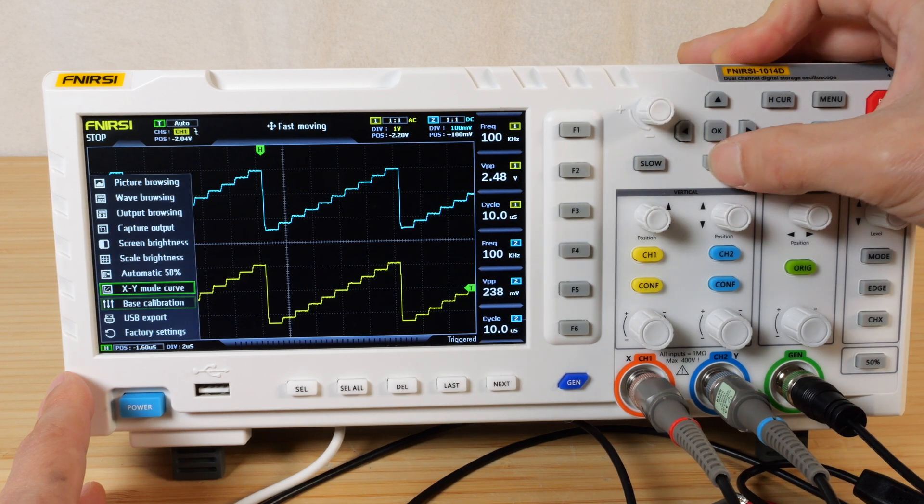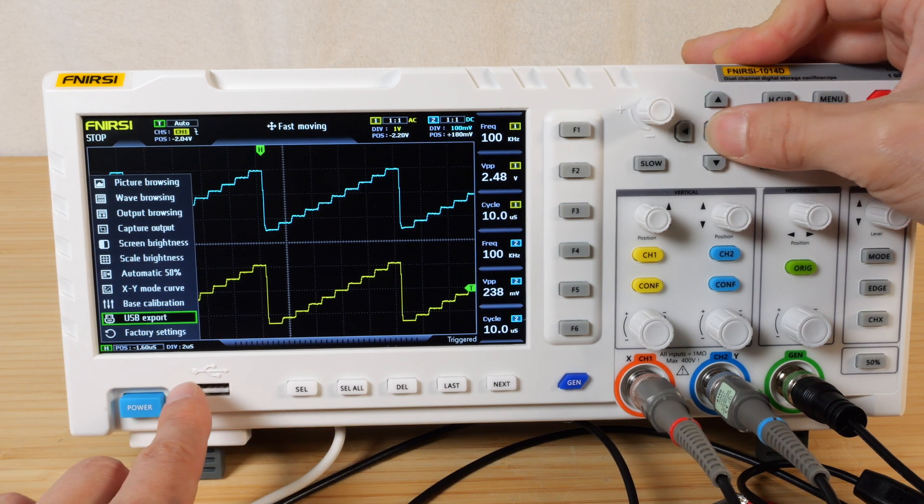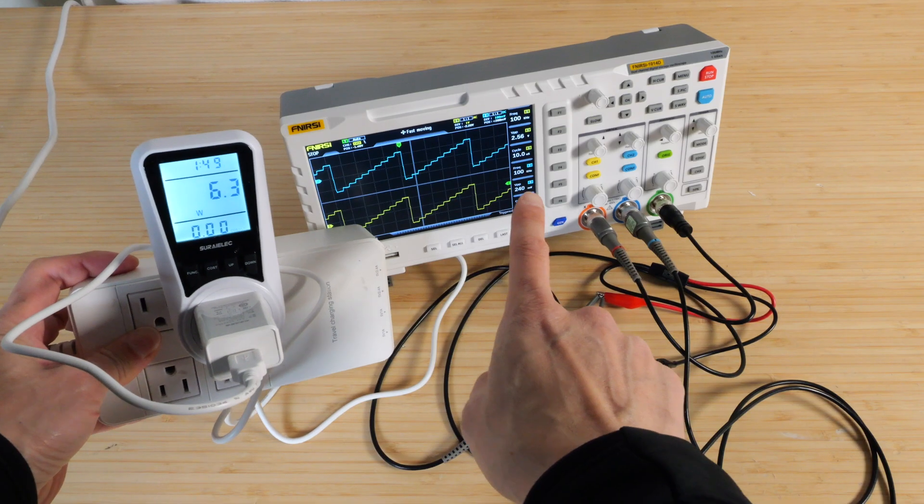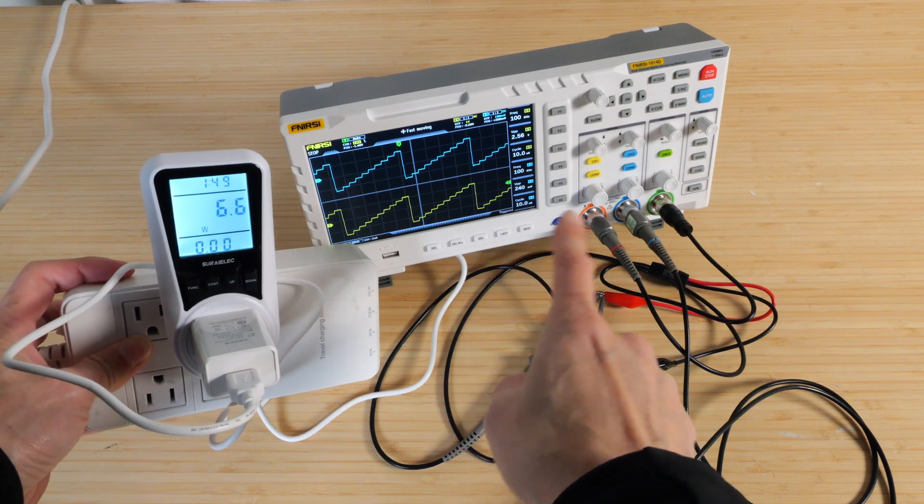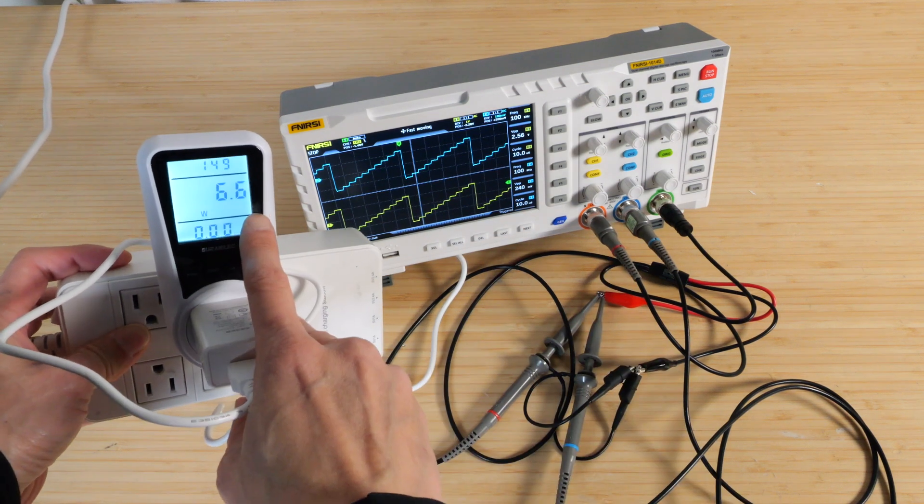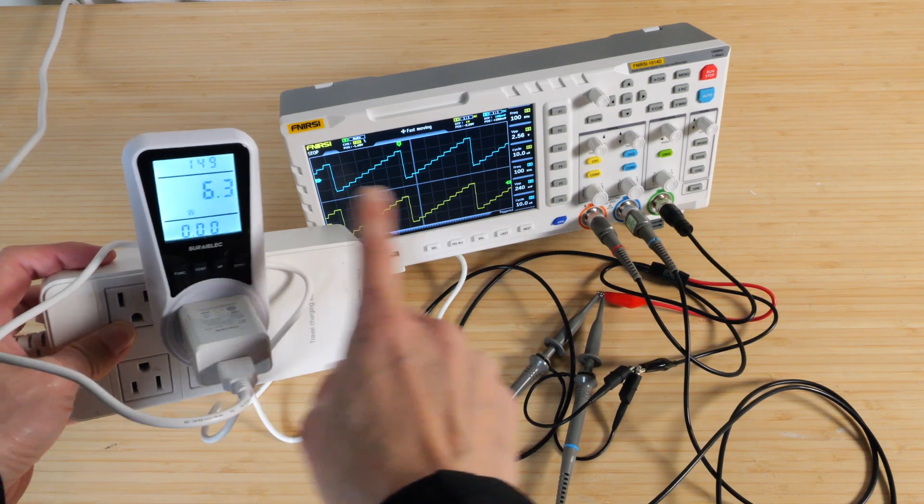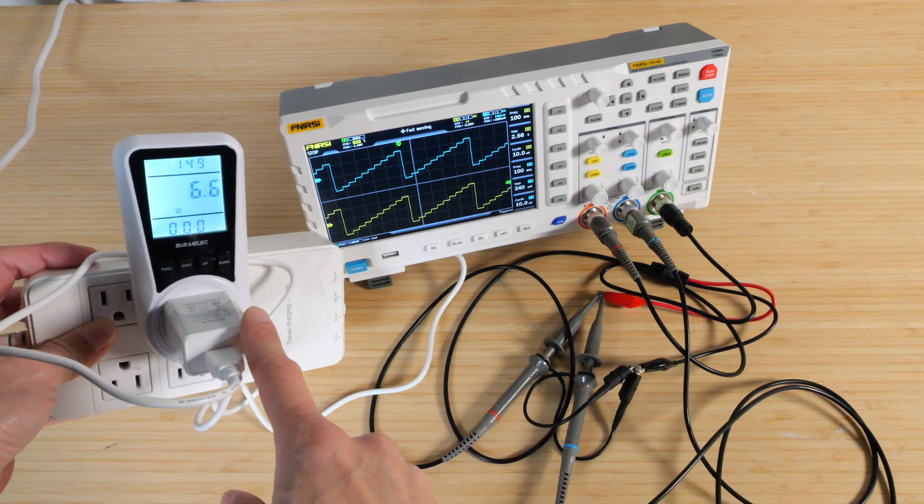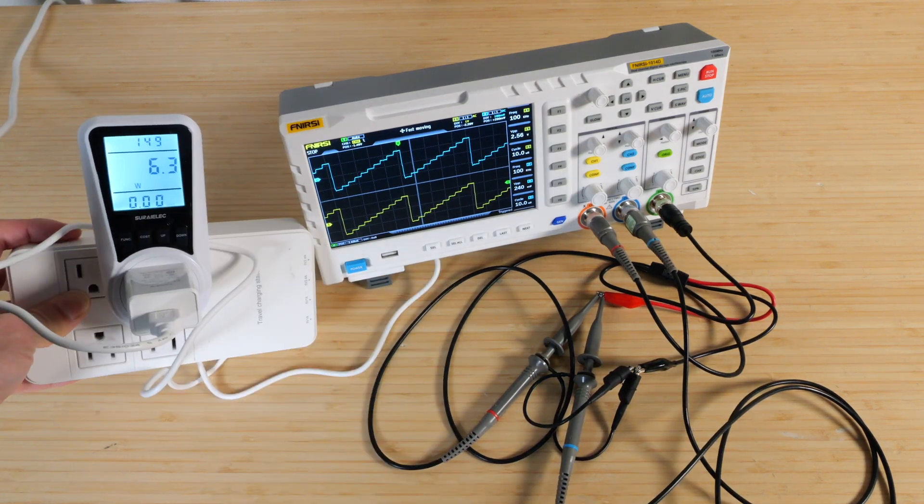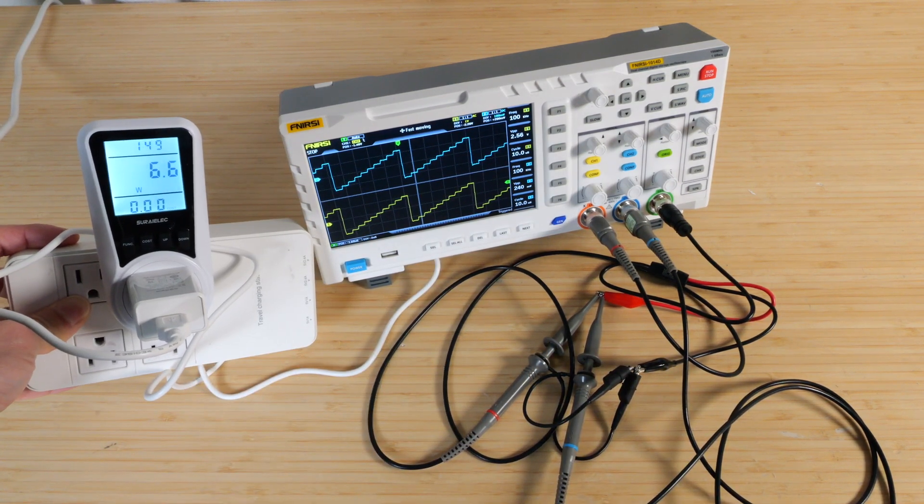Base calibration. We have to pull out all the probes to calibrate. Let's not do that right now. USB export. So we can plug in a USB and it's going to export all the data it has. Even with it outputting all this funny signal and using both channels, it's still using only about 6.6 watts for the entire thing. The AC adapter is capable of 10 watts. So this is a very power sipping device.